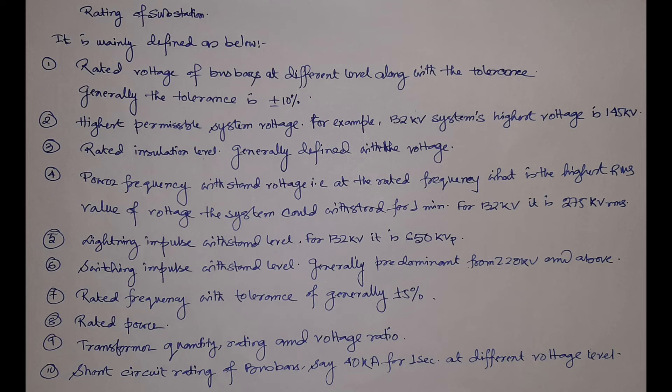Then there comes the rated insulation level, generally represented by the rated voltage, maximum system voltage, lightning impulse voltage, etc. Then comes the power frequency withstand voltage — this is the voltage at rated frequency at the highest RMS level that the system can withstand. For example, at the 132 kV level the power frequency withstand voltage is 275 kV RMS for one minute. That means at rated frequency, the maximum RMS voltage the system can withstand for one minute.